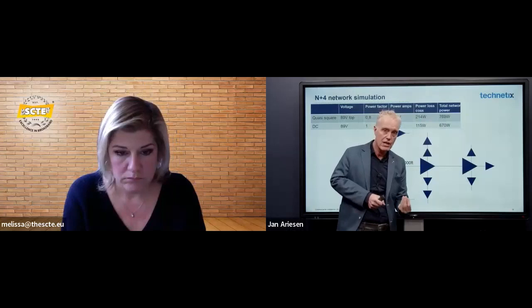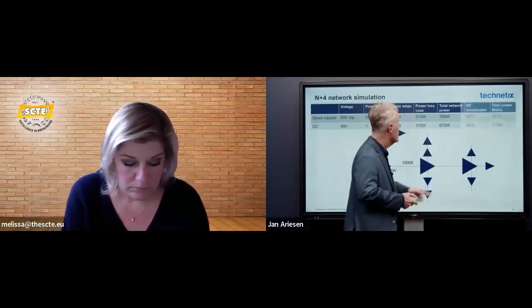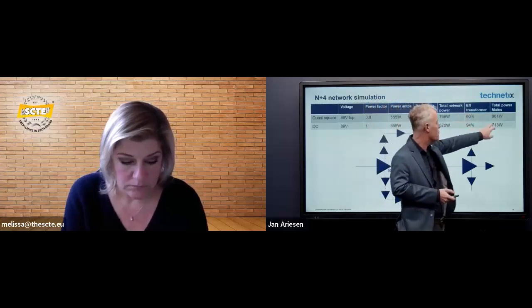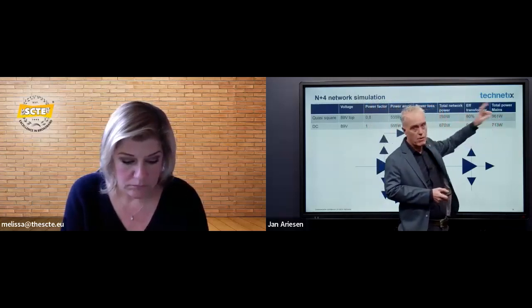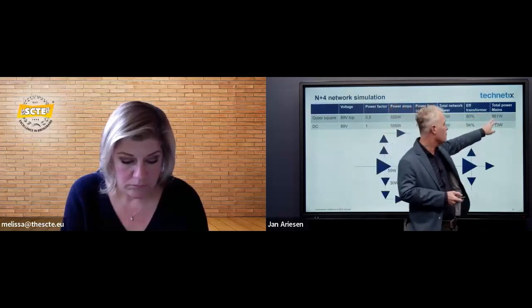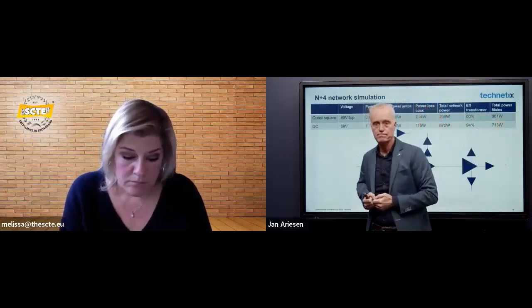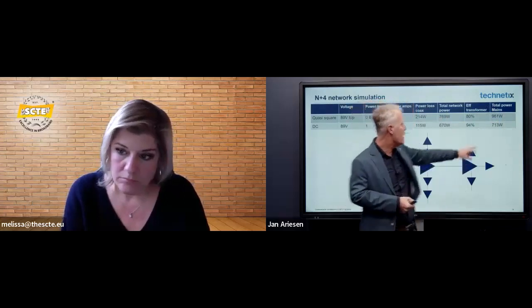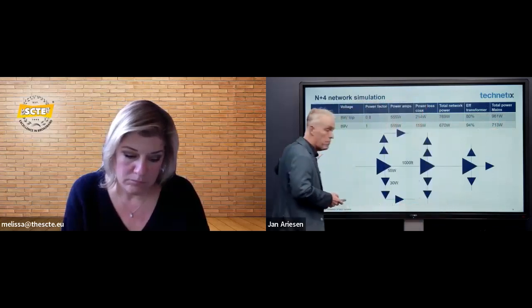Then I have the second step, as we saw: with ferroresonant transformers, we have an efficiency somewhere between 69 and 83%, while the efficiency of an AC-DC converter is around 94%. And that, of course, gives you the other saving. Therefore you see that this time, with the quasi-square, we need to draw 961 watts out of the network. And if I go to DC, I only have to draw 713 watts. So that's the difference measured on the power side.